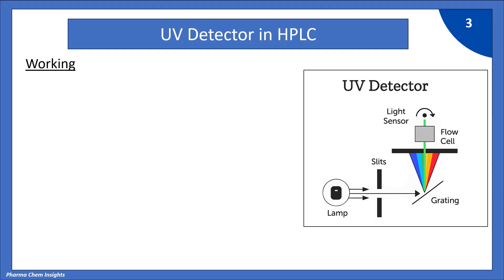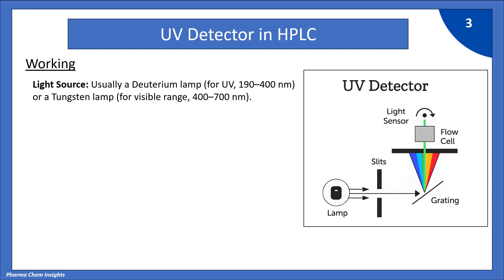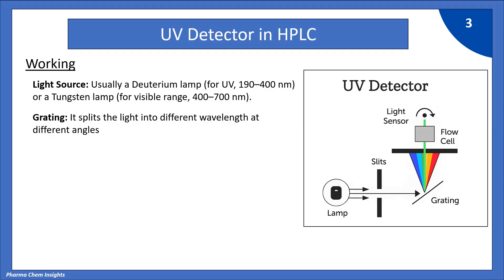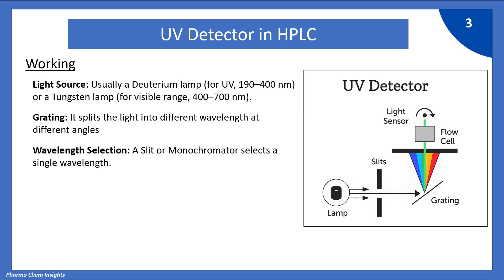Let's see each component one by one. First is the light source — it's usually a deuterium lamp for the UV region 190 to 400 nanometers, or a tungsten lamp for the visible range 400 to 700 nanometers. Light passes through a slit onto a grating, which splits the light into different wavelengths at different angles like a rainbow. The second slit, or monochromator, selects a single wavelength — for example, 273 nanometers — which then passes through into the flow cell.